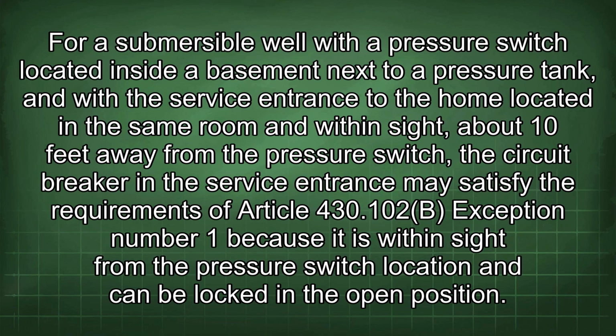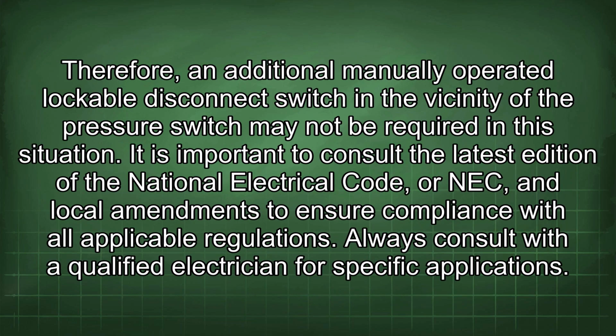For a submersible well with a pressure switch located inside a basement next to a pressure tank, and with a service entrance to the home located in the same room and within sight, about 10 feet away from the pressure switch, the circuit breaker in the service entrance may satisfy the requirements of Article 430.102(b) exception number 1, because it is within sight from the pressure switch location and can be locked in the open position. Therefore, an additional manually operated lockable disconnect switch in the vicinity of the pressure switch may not be required in this situation.